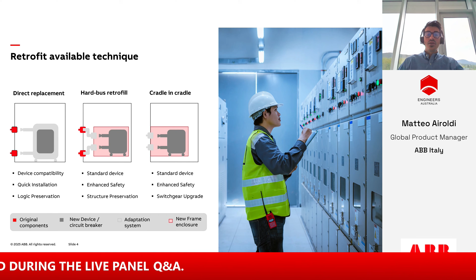The advantages include use of a standard device, which simplifies future maintenance and ensures long-term availability of spare parts; enhanced safety, because the new breaker brings modern protection features such as advanced electronic trip units, arc fault detection, and remote monitoring capabilities; and structure preservation, since the original switchgear panel remains in place, avoiding the need for civil work or major rewiring.